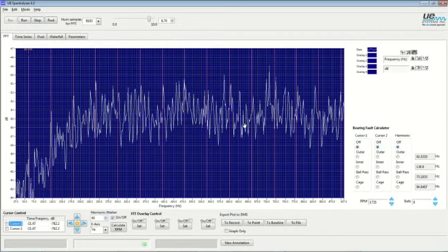Now, another type of event related to vibration would be a mechanical issue. You would have a similar spectrum, but all the 60 hertz peaks would hit. I will play an example of that shortly to show you the difference in the frequency spectrums. But what will be absent on that type of issue is this frequency noise, or the activity that we see going on between here.